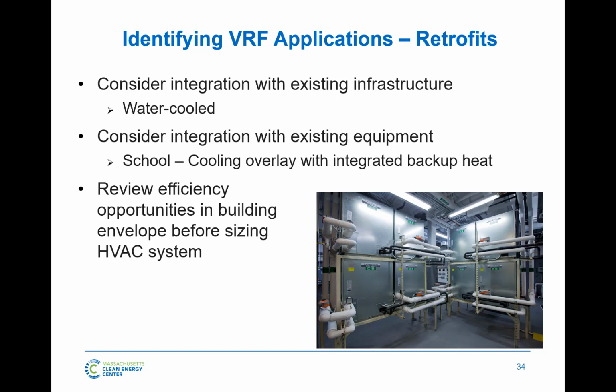and that's a good option for retrofits. And then it's always worth mentioning to review different efficiency opportunities in the building envelope before sizing the HVAC system. So don't just take a VRF system and say, well, there's a 300,000 BTU boiler in here before, I'm going to put a 300,000 BTU VRF system in and call it a day. With VRF systems, you really have the ability to right-size the equipment for your building. So make sure you take advantage of any low-hanging fruit so that you can right-size your VRF system and get the most efficient package rather than just the efficient piece of equipment.